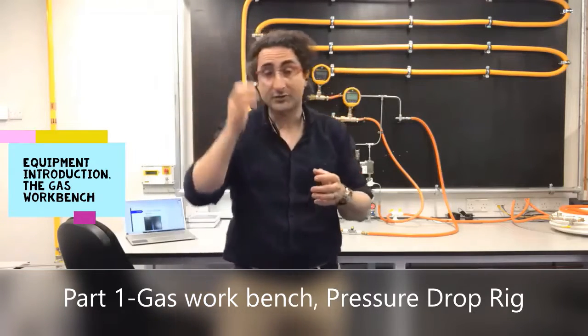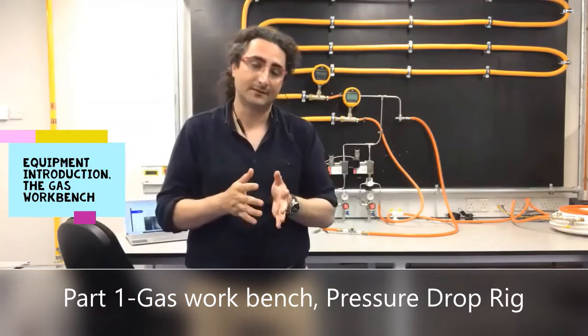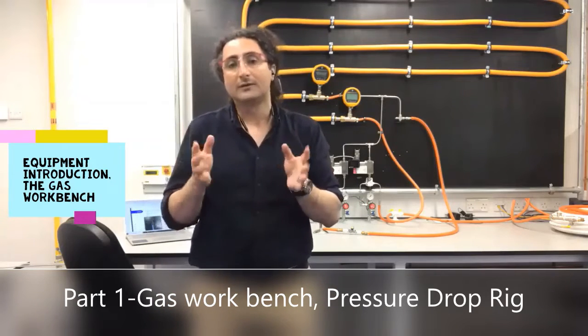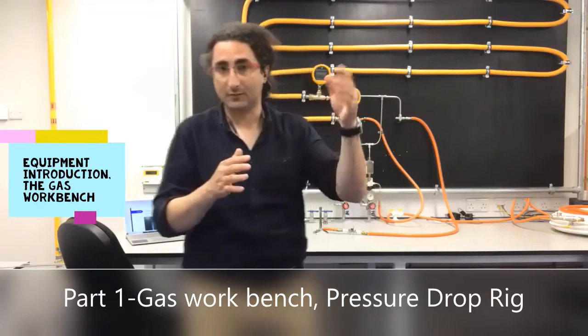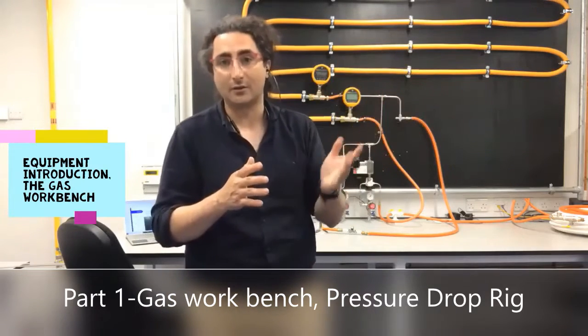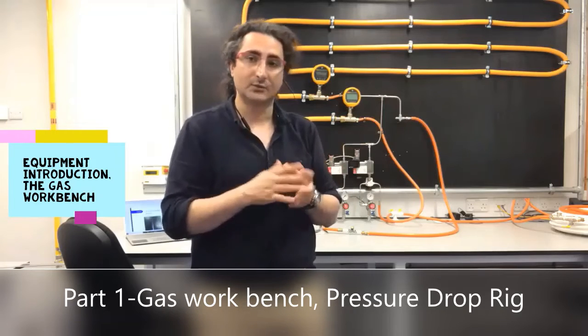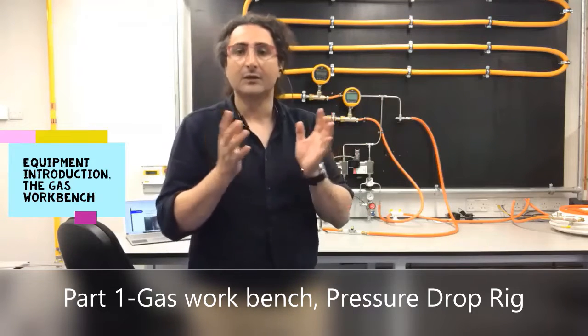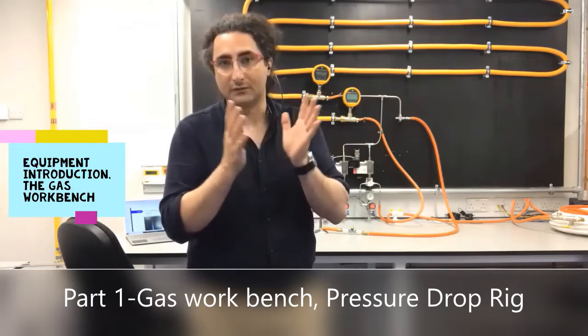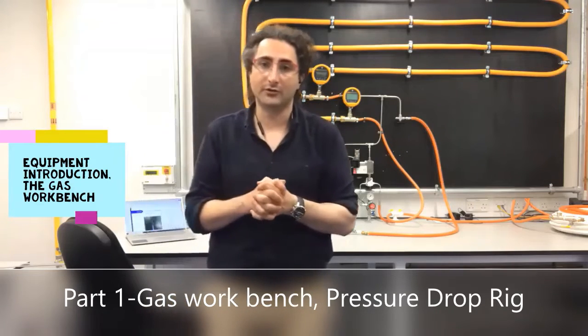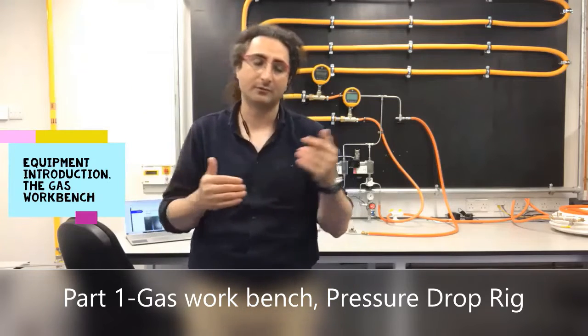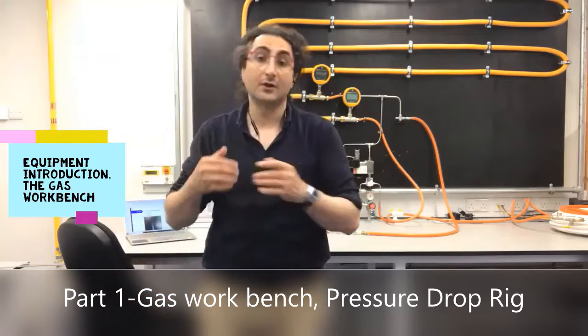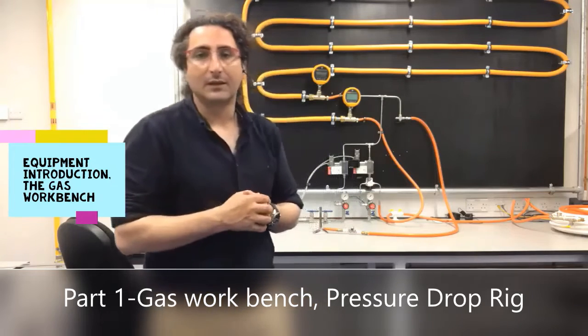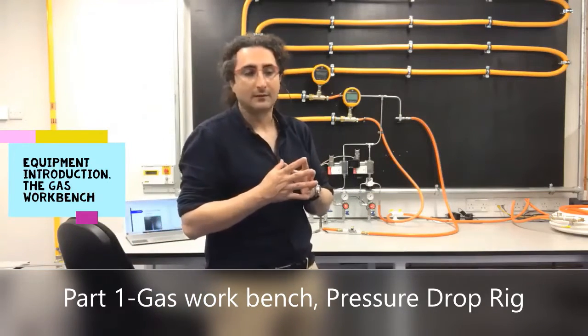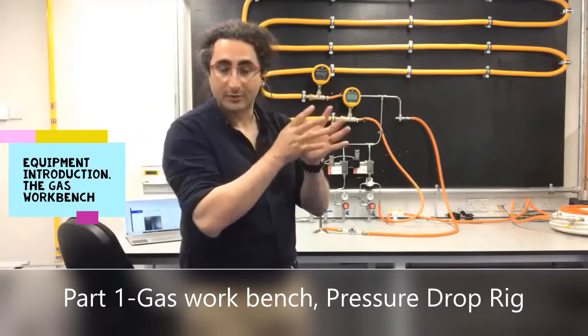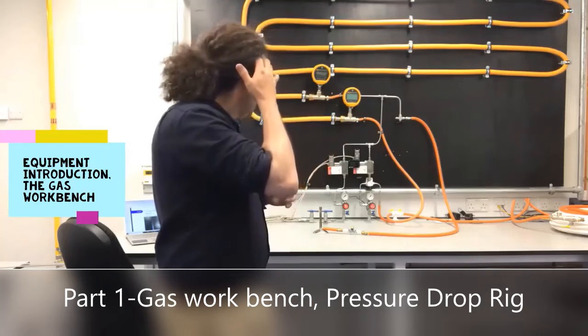But here the project is testing hydrogen blends. We want to blend hydrogen. The source of the hydrogen is green sources. We call it green hydrogen, blended with natural gas, mainly methane, to see what impact these blends have on the operational variables. For example, on pressure drop, on flow rates, on density, calorific value, leak, and leakage. And they are the important objectives of the project.